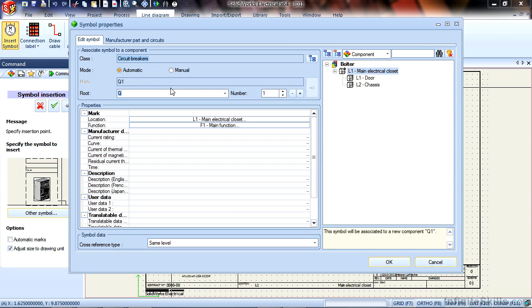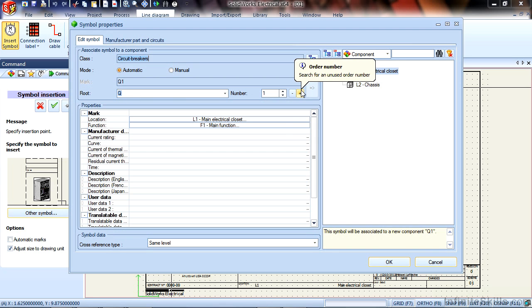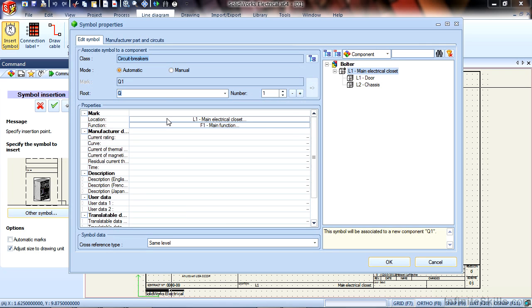If you click anywhere on the screen to place the symbol, you are presented with the Symbol Properties menu, confirming that it's a circuit breaker classified component, and it's also presenting us with a root number. So the root of Q is indicative of a circuit breaker. This Q can be set to any number or letter that you wish. The number next to it is a suffix, so this is the first circuit breaker we're placing, and it's called Q1. It concatenates that as one mark number. Other information can be applied to the symbol as you drop it on. So if you have a description of what the function of this circuit breaker is, you could apply it here under the description.